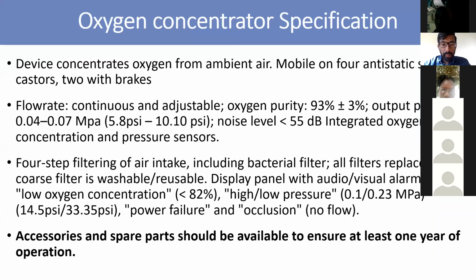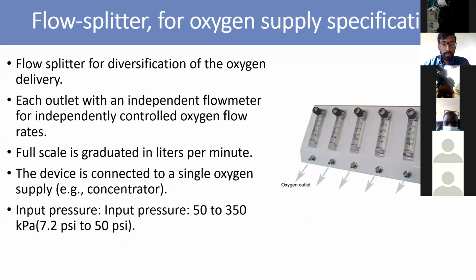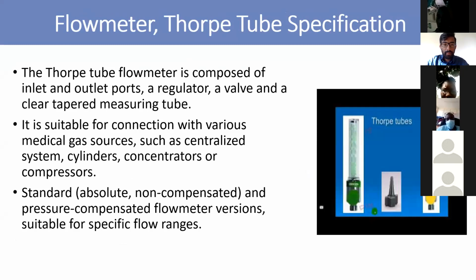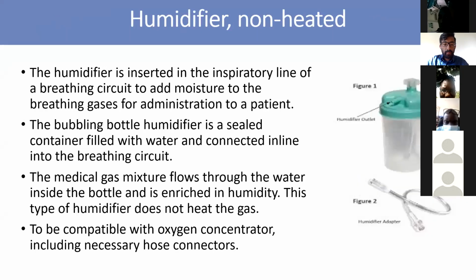This is the oxygen concentrator specification that you normally see when your hospital purchases one. You're going to see all these details, like the oxygen purity has to be more than 93%, some 95%, depending on the brand and model. Flow splitter: for oxygen supply specification, you can add on flow if your oxygen concentrator has an extra output, so you can add on more flow for more patient control. Flow meter: this type of flow meter you can normally see on an oxygen cylinder sometimes. Sometimes you end up seeing it in the oxygen concentrator itself. So it depends.